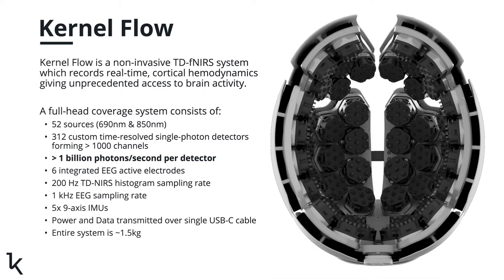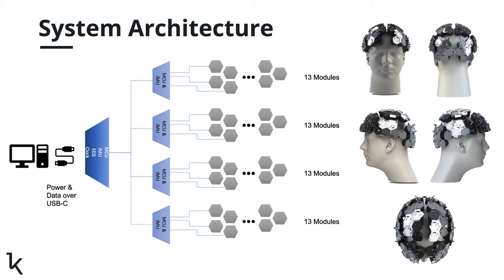With this background on time domain, it is clear why this technology is compelling. However, it has never been developed to a point of accessibility where it can be widely used and new applications could be freely explored. We designed Kernel Flow to overcome this. It is a modular system designed for full head coverage. It includes a combination of high performance custom detector circuits with high photon count rates, dual wavelength laser diodes, inertial measurement units, EEG channels, and it uses only a single USB-C cable to provide power and bi-directional data transfer. The system was designed with a hierarchical architecture so that we could meet the data transfer and timing requirements that enable full head coverage while also allowing for adaptation to different applications that may only require regional coverage.